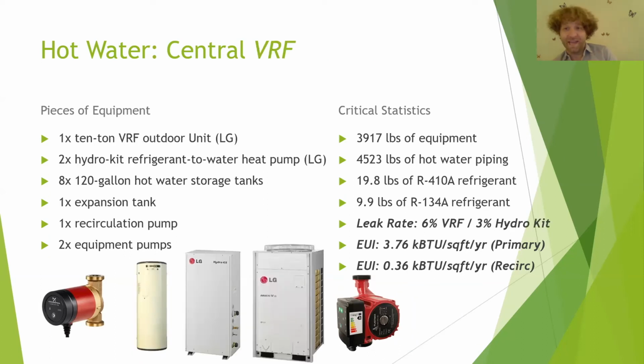The most complicated and not well known system is using VRF to heat hot water. There's actually a secondary compressor that heats the hot water: you have a VRF compressor on the roof, and you have a secondary compressor down in your mechanical room that heats the hot water. And these systems are complicated, and not many manufacturers do it. Like Mitsubishi pulled theirs out of the American market, so they don't do it anymore.